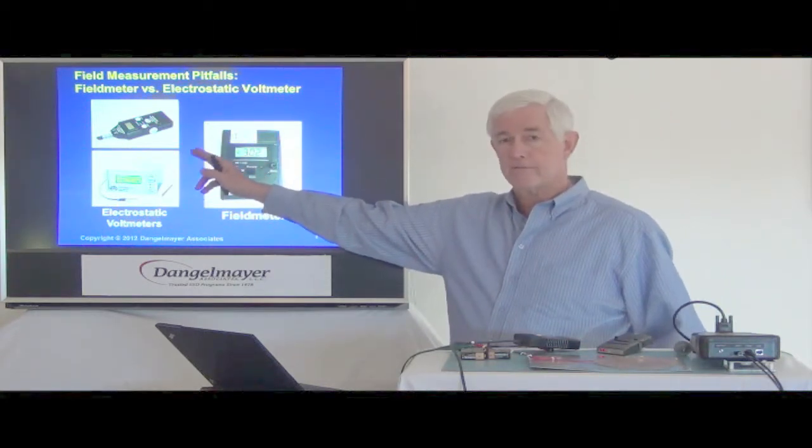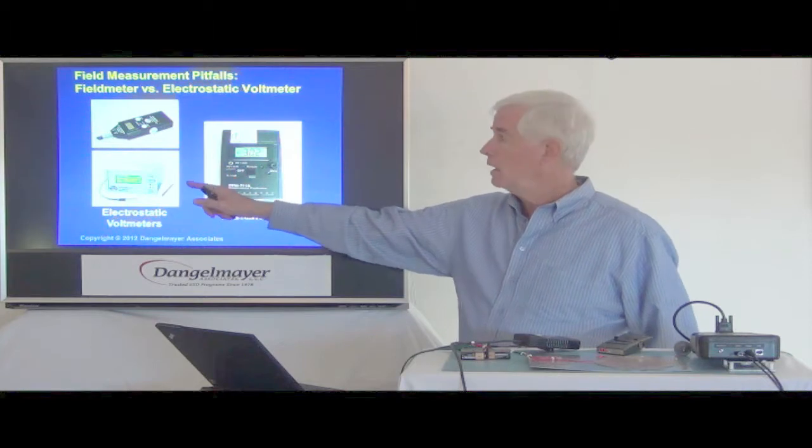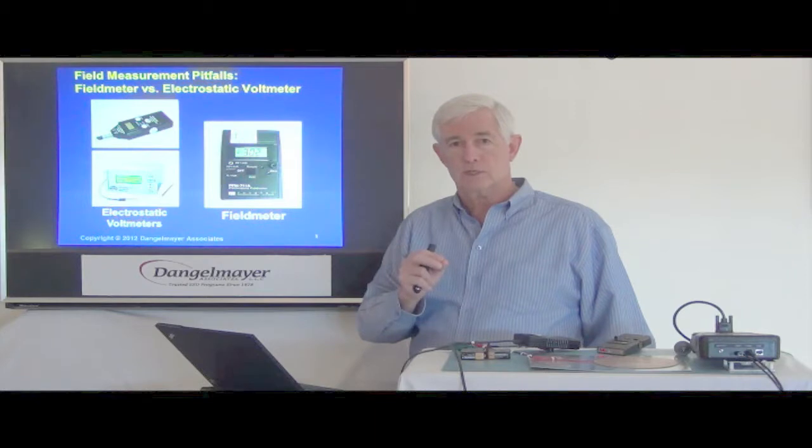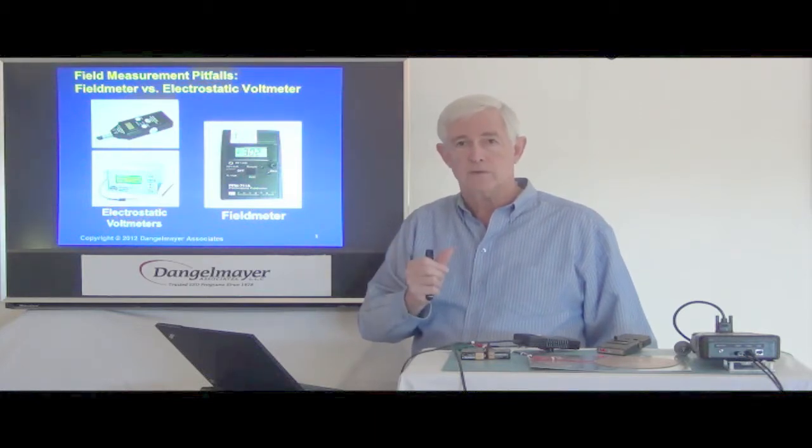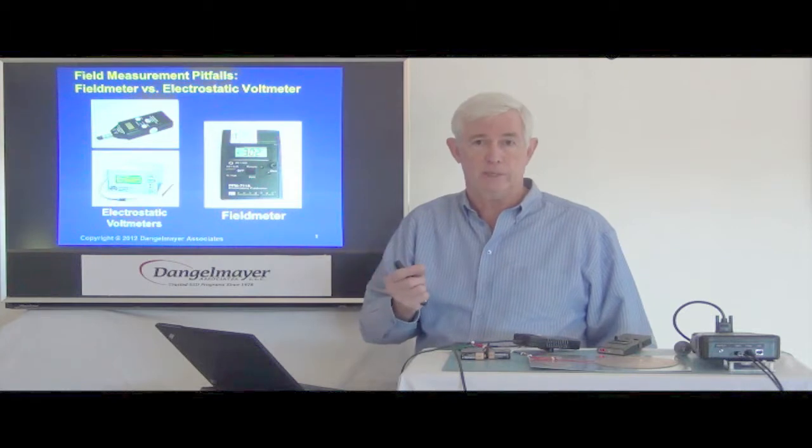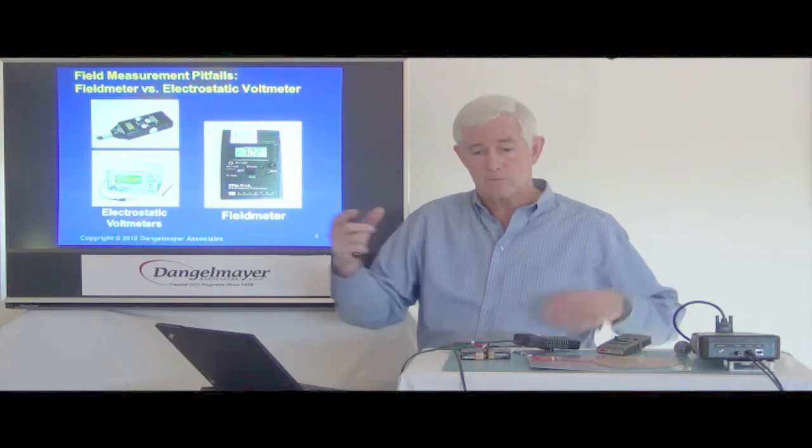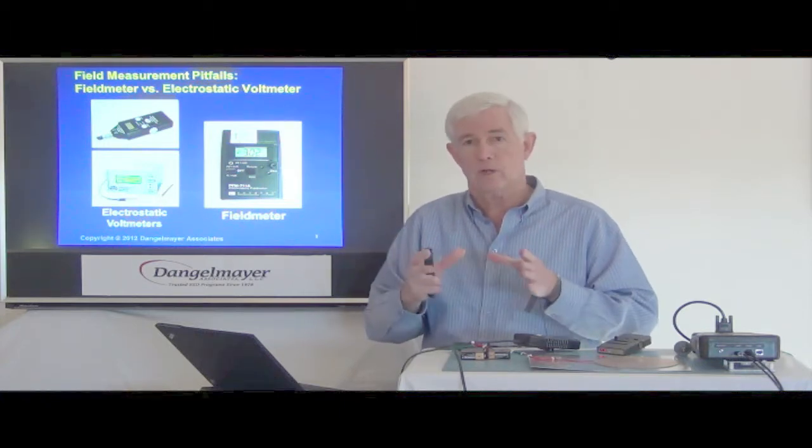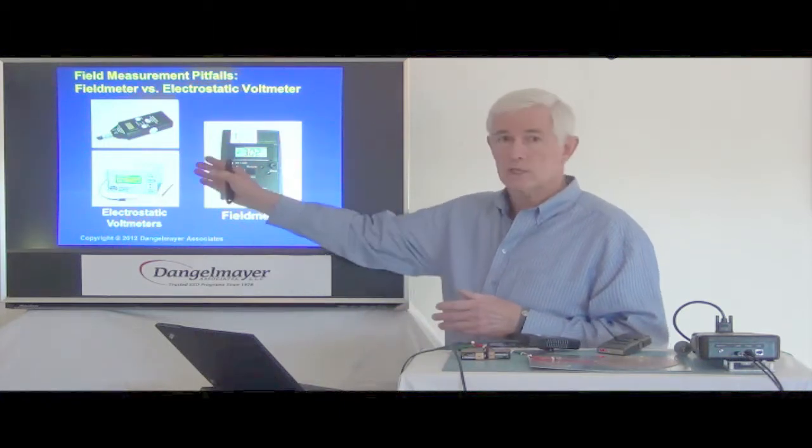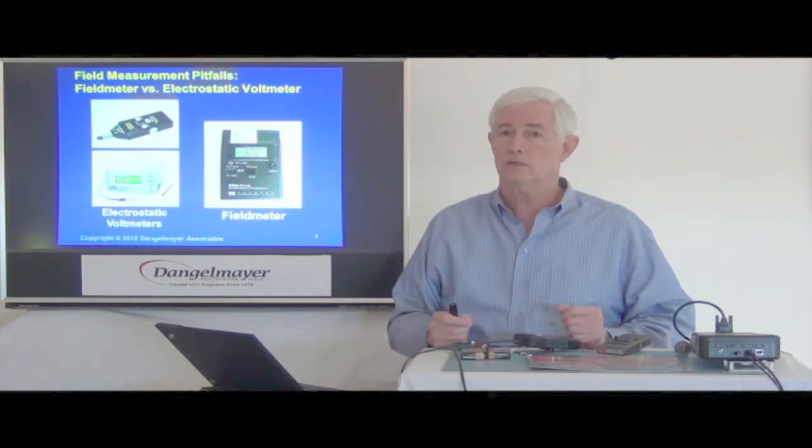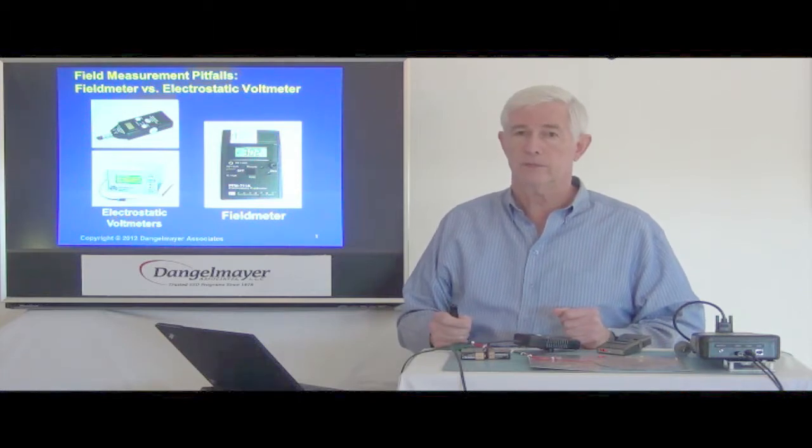The electrostatic voltmeter, on the other hand, can be set to make measurements at a much closer distance. The rule of thumb of four to one still applies, but the spacing for the recommended distance on the measurement can be down to just three to five millimeters. So that reduces the field of view and gives you more accurate measurements on smaller objects. Very important distinction, and typically the electrostatic voltmeters are not well known, and yet they're a very powerful tool to have in your kit.